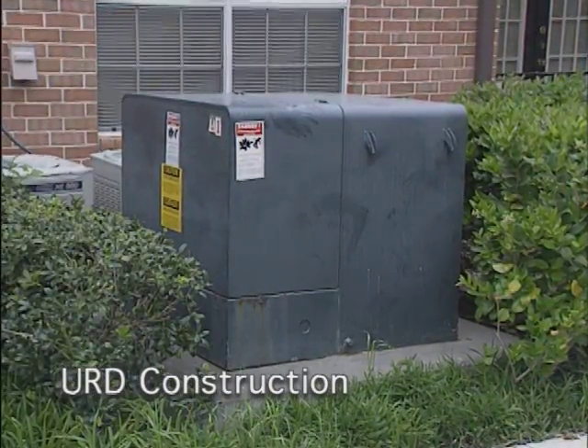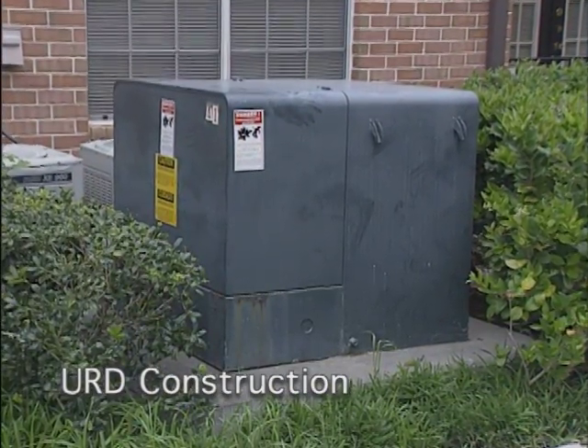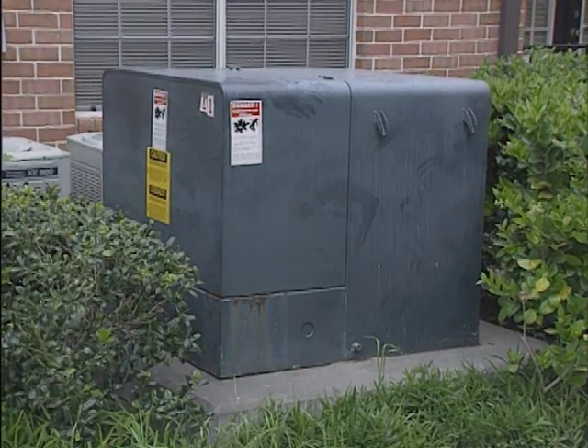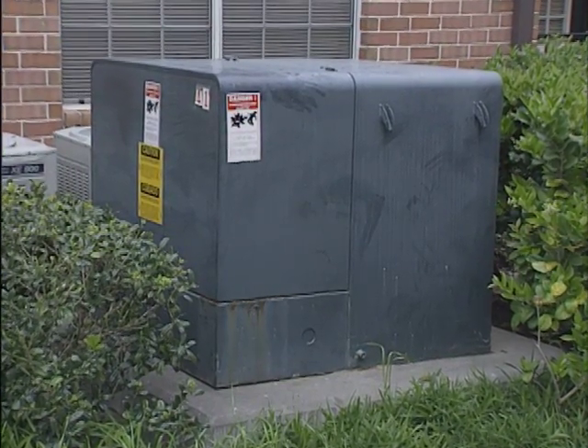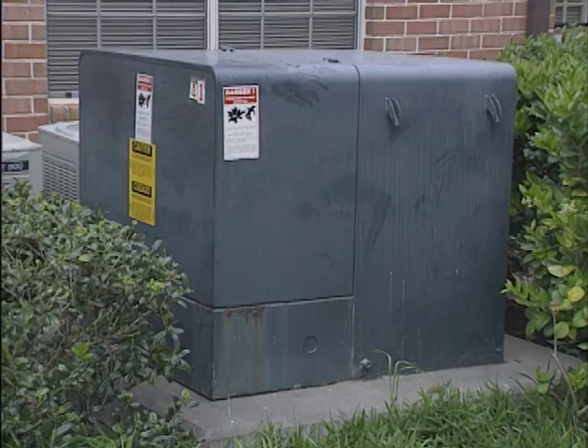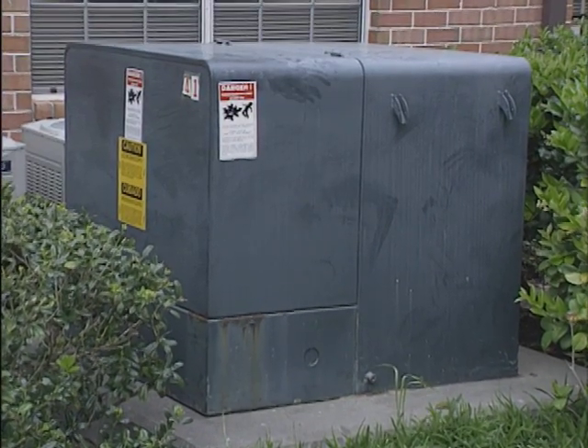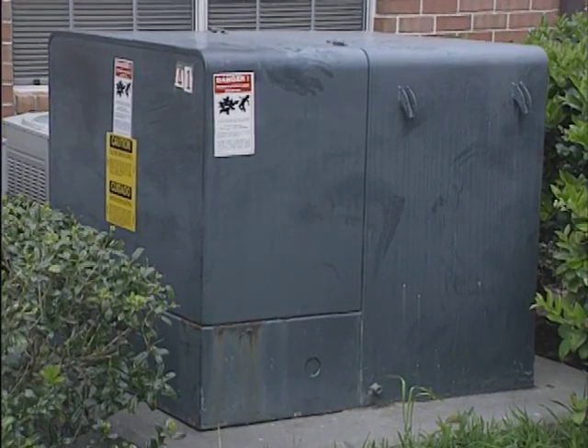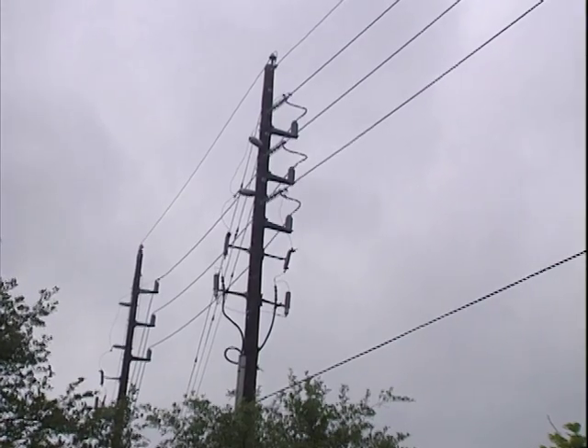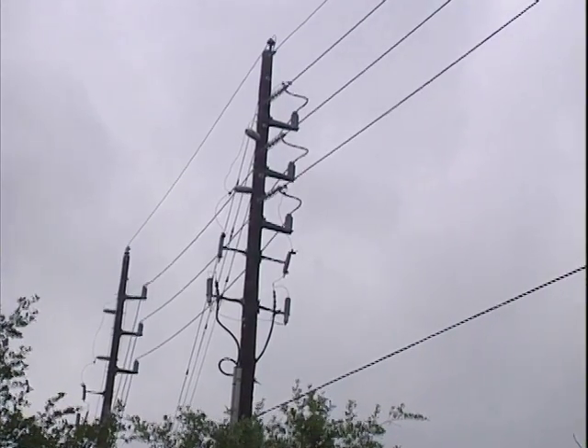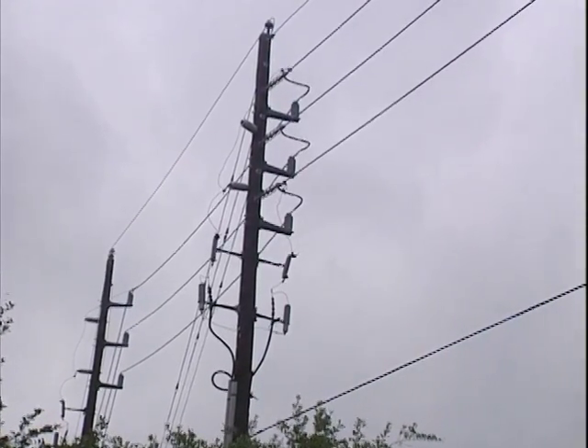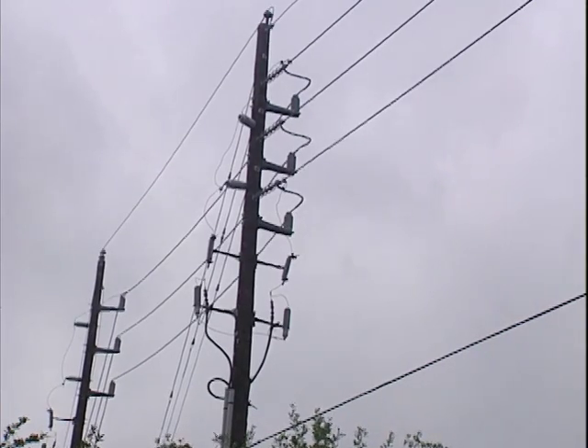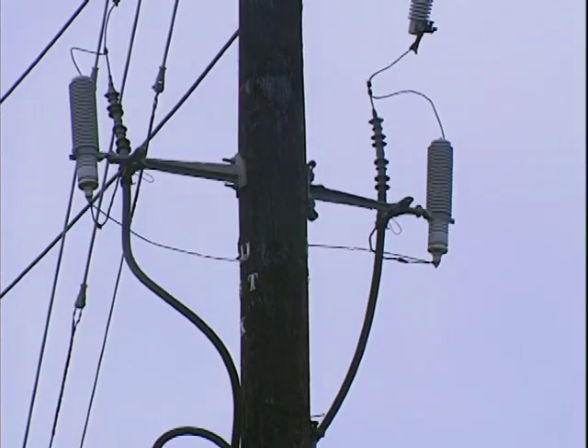URD construction can be found throughout our service area. While you may not be actively involved in this part of the restoration process, just be aware that you could be restoring an overhead line that feeds underground distribution. Each URD loop has 2 terminal poles with the loop split either at a midpoint transformer or at the terminal pole. For your safety, assume all URD risers are energized until tested and grounded.